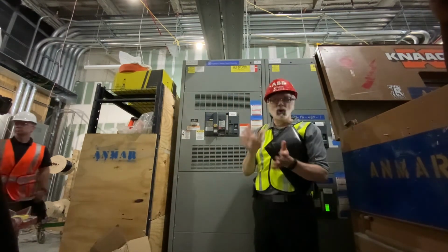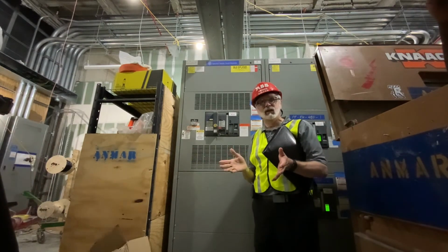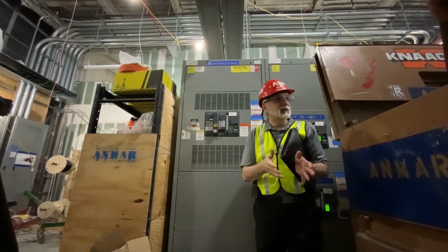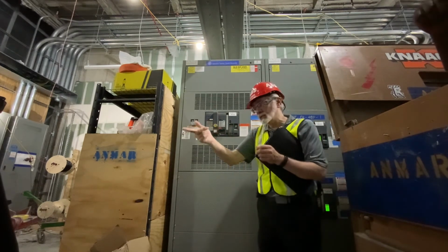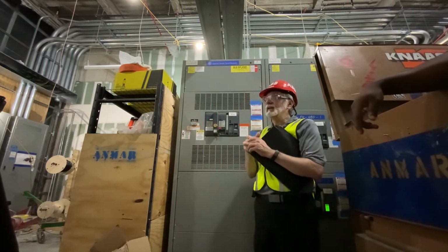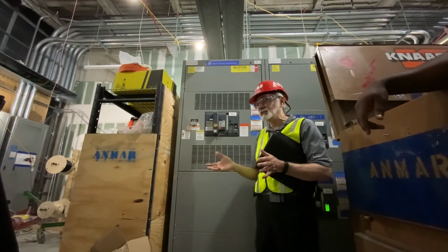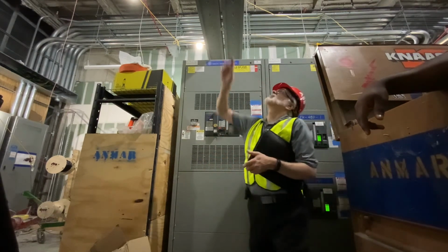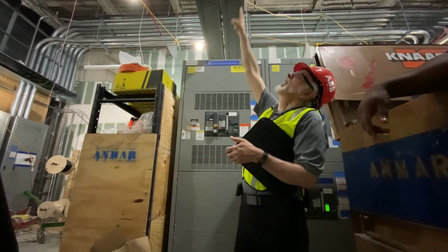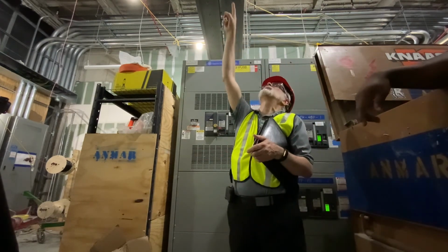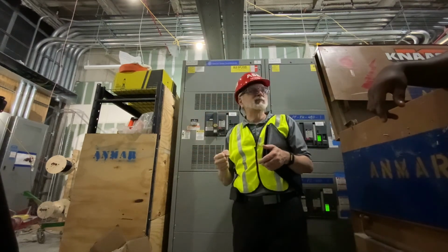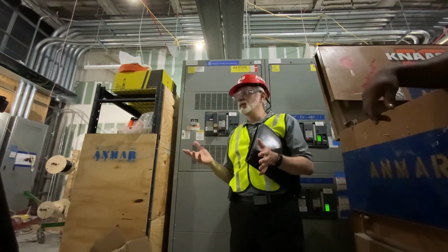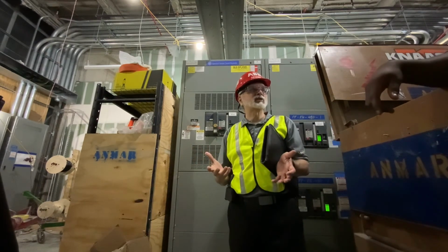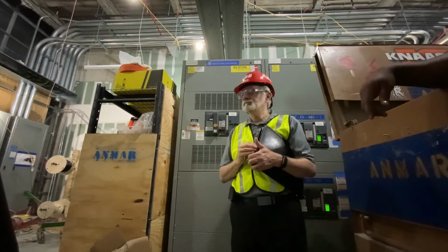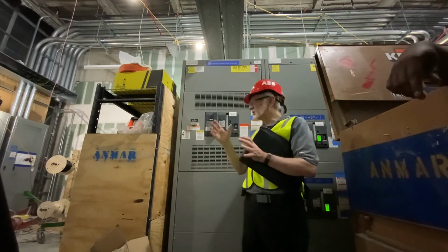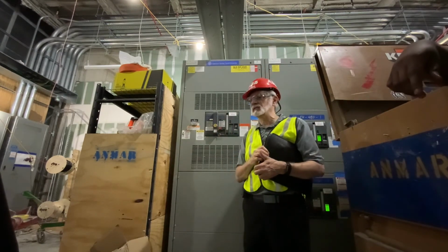The thing about busway is it's very good, it's very practical, it's all enclosed, and it's got insulated bus. The only thing you really need to do from a maintenance standpoint is, again, keep it clean, but most importantly, and this goes to the question you had a little earlier, if there's one thing you want to check the torque values on, it's the bus joints. Everywhere these pieces of bus are tied together, there is a bolt. Check those bolts annually to make sure they're tightened to the proper torque so that they don't work loose. Any questions on the switchboard or the busway portion of the unit substation?